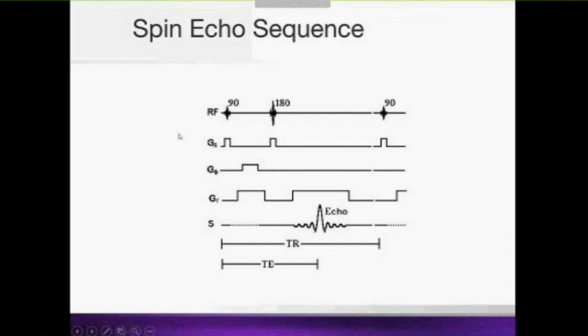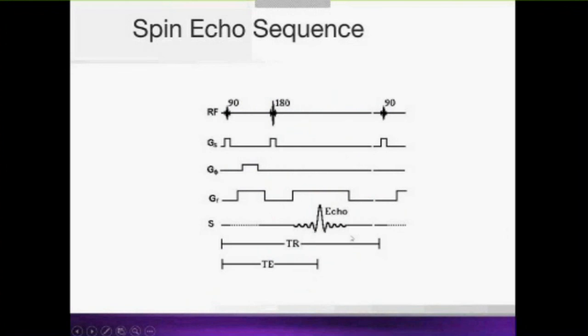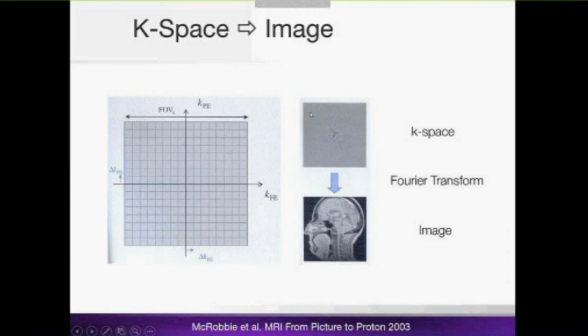To summarize: to get an echo and localize it, we need the RF pulses — in spin echo, a 90-degree pulse followed by a 180-degree pulse — and we need the slice-encoding gradient, the phase-encoding gradient, and the frequency-encoding gradient, all applied in the correct order. That is why it is called a sequence. Each repetition fills one line of k-space, and we repeat the whole process again and again until k-space is completely filled.